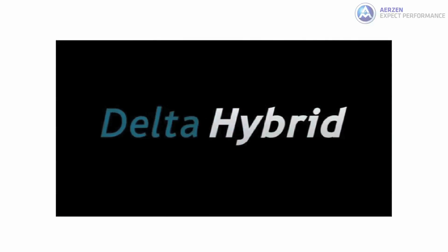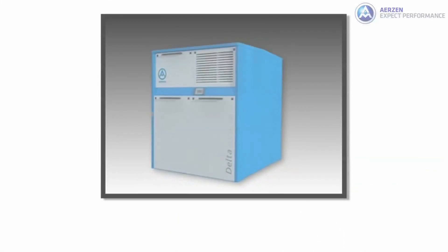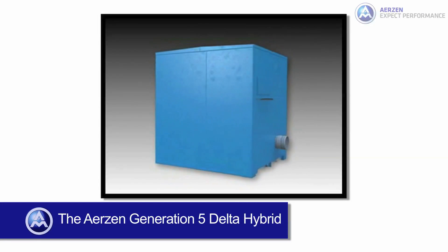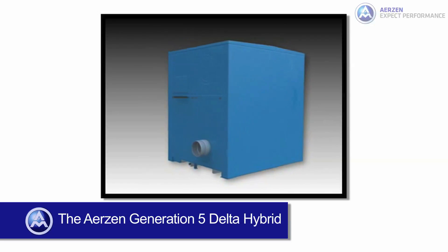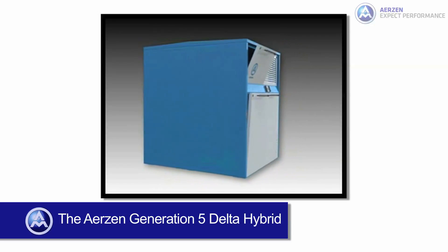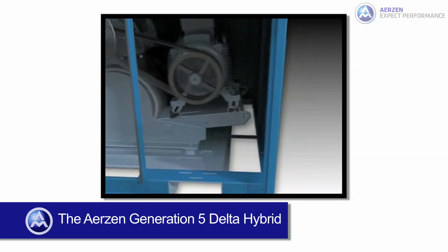The Aerzen Generation 5 Delta Hybrid is a rotary lobe compressor, the result of a synergy between the rotary lobe blower and screw compressor technologies. The Delta Hybrid was developed with the focus on increasing energy efficiency and achieving a significant reduction of energy costs and greenhouse gas emissions. Wire-to-process energy usage reduction can exceed 30% over typical positive displacement blowers, depending on operating conditions and turndown range.